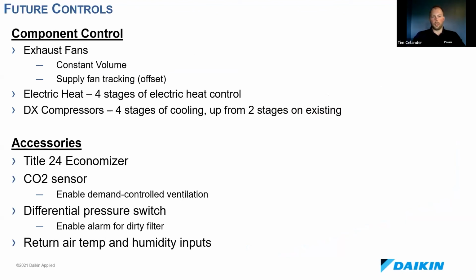And as we talk about the new cabinet, there are some additional features. We need more controls, and I just wanted to highlight some of that here. So with those exhaust fans, we're able to operate in constant volume or a supply fan tracking offsets as your fan modulates. So when your exhaust fan, the electric heat, you can now get up to 4 stages on this new cabinet or continue to use SCR heat. And split DX systems, you can get 4 stages of cooling, where today, lower tonnage units, we're offering 2 stages in the controlled PreciseLine. And with a larger cabinet, we have a larger controls box.